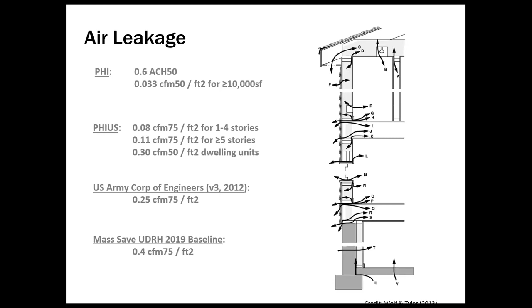So it definitely addresses the different types of projects out there, whether they be tight boxes or very spread out components, with different requirements for larger buildings of greater than 5 stories, and specific compartmentalization requirements for dwelling units as well. Just as a comparison, the Army Corps of Engineers has roughly 3 times the level of air leakage allowable as the PHIUS and PHI requirements.